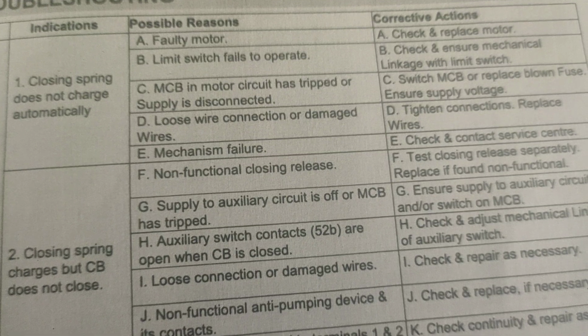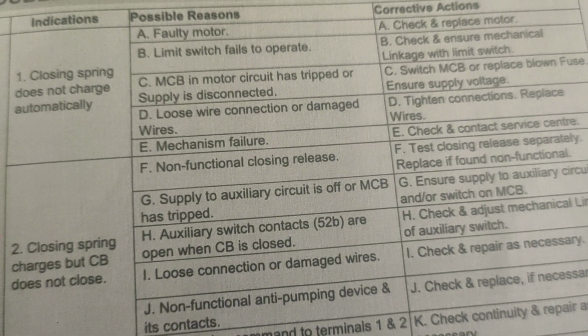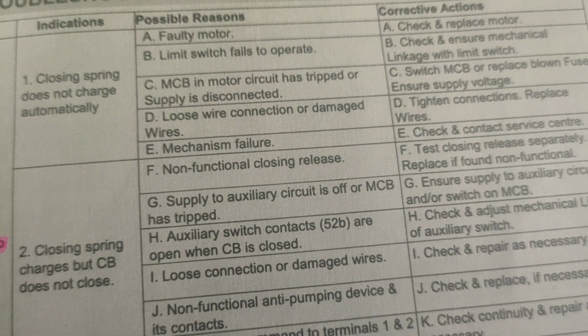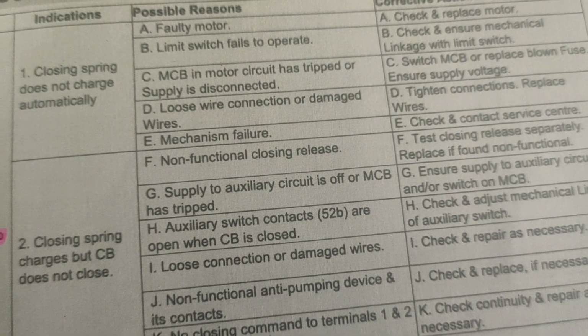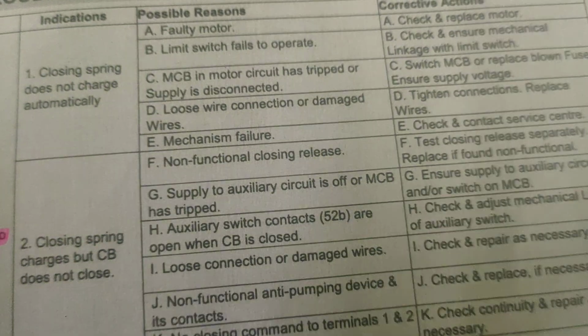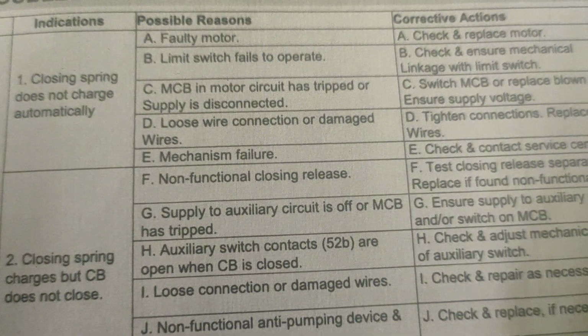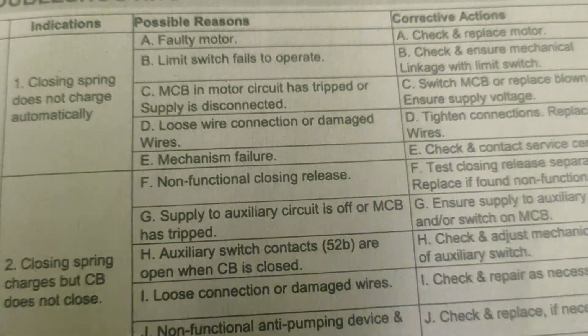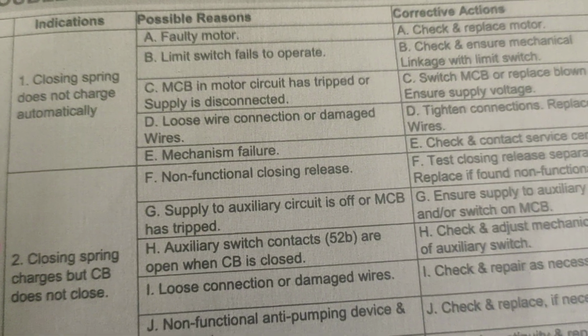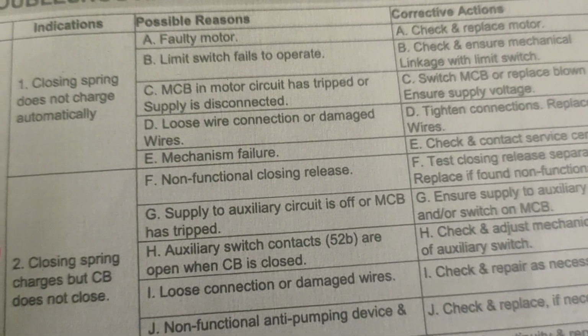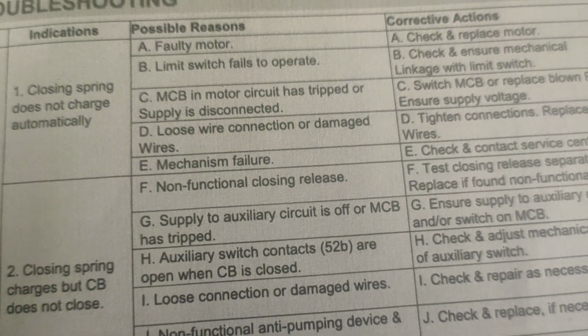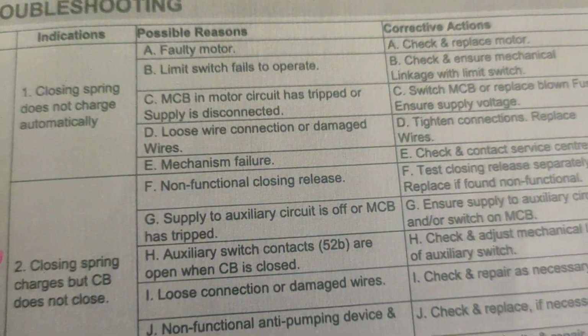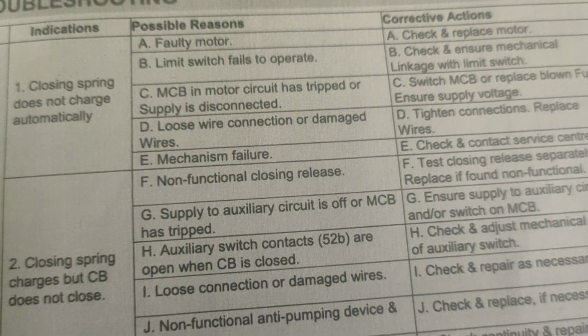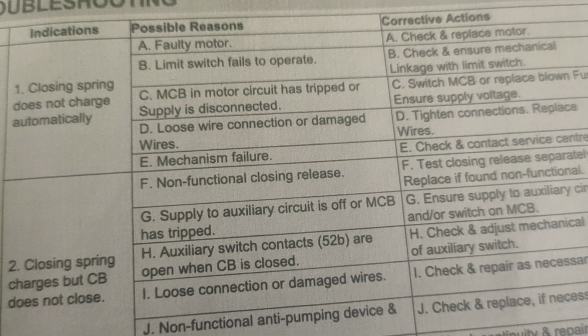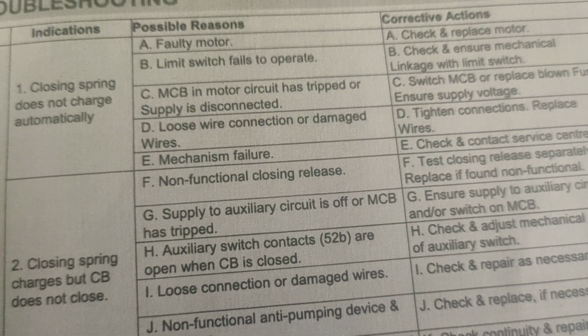In the faulty motor case, you have to check that the motor is not short of the torque that can close the circuit breaker. So you have to immediately replace the spring charging motor from the spare. If you change the spring charging motor from the spare, the required torque will be developed and the circuit breaker will easily close. The MCB of the motor circuit may also have tripped due to some problem inside the motor, so the supply cannot continue to the motor.